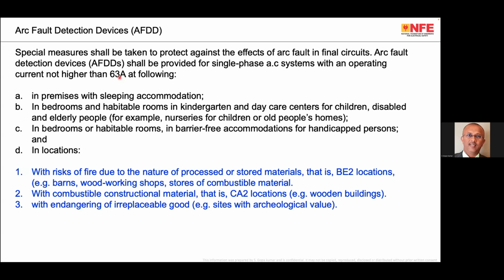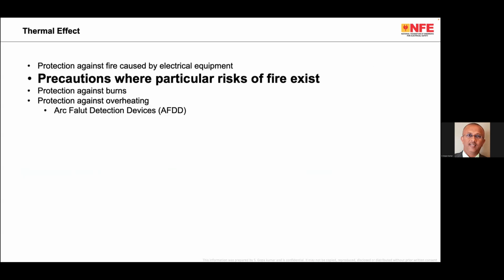After 2 years, they replaced or they bypassed or they took away the entire AFDD. So even though there is a solution available, please use it according to the recommendation of the standard. Don't try to use it everywhere. So these are the measures which are recommended for protection against fire caused by electrical equipment. As I said, please note that I am not going deep into the subject because it's a very big subject, because it's like connecting several standards. Once we start with IS 732, then we have to go to the next. It goes on in a large way.